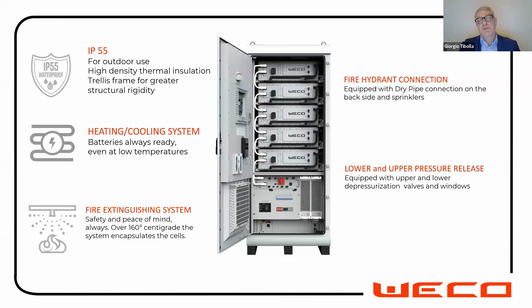The product is IP55 with heating cooling system, with fire suppression, and there is a lower and upper pressure release. So if inside the battery cabinet the pressure is too much, there are valves and windows, and thanks to them the pressure can go out.